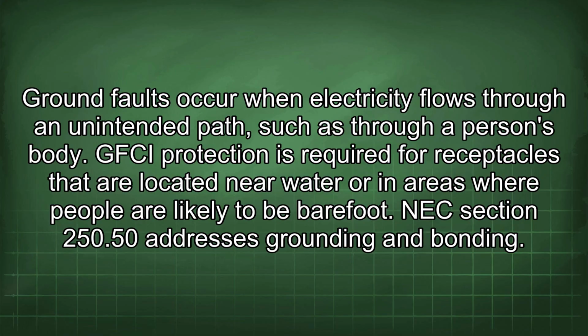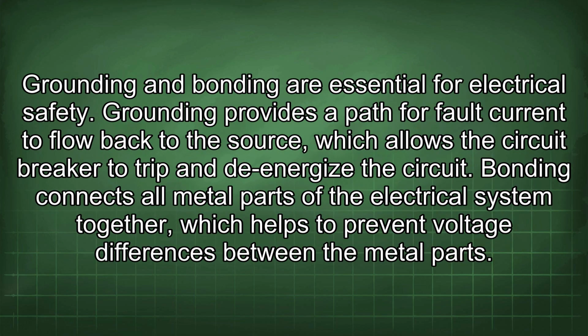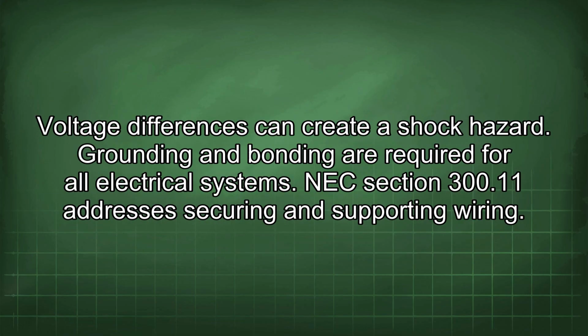NEC Section 250.50 addresses grounding and bonding. Grounding and bonding are essential for electrical safety. Grounding provides a path for fault current to flow back to the source, which allows the circuit breaker to trip and de-energize the circuit. Bonding connects all metal parts of the electrical system together, which helps to prevent voltage differences between the metal parts. Voltage differences can create a shock hazard. Grounding and bonding are required for all electrical systems.